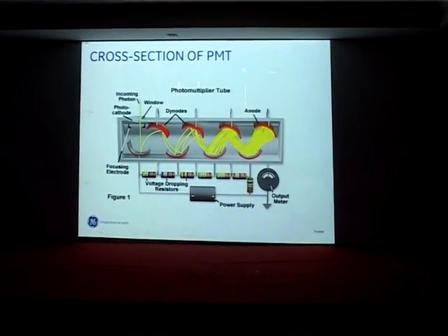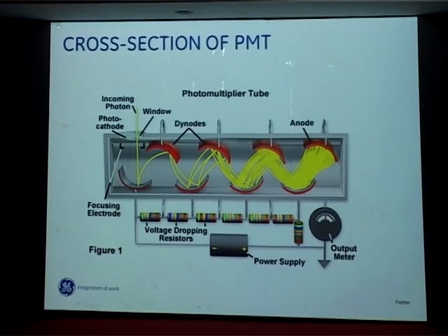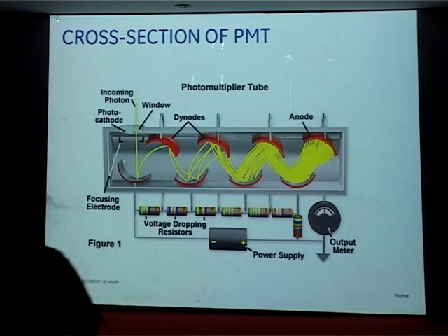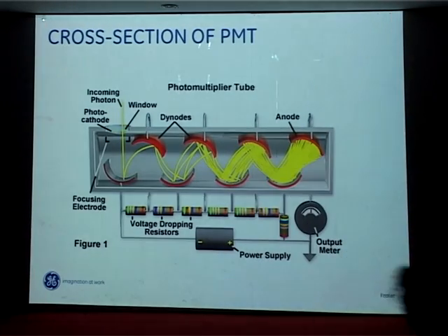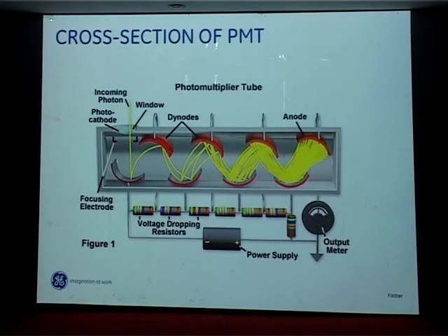The photon emitted by the scintillation crystal produces a quite small signal that needs to be amplified. The photon is picked up by the photocathode through a window — the photocathode is coated with a photoemissive substance. A focusing grid directs electrons onto a dynode, and each successive dynode is maintained at a higher potential, causing amplification. The amplification is almost 10⁶ to 10⁸ times, so a small weak signal becomes very powerful by the time it exits the photomultiplier tube.